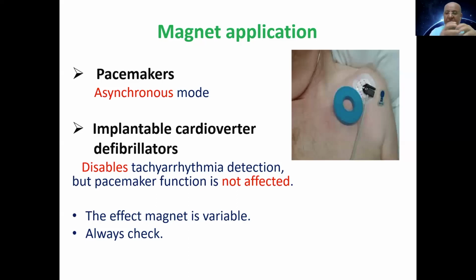So when a magnet is applied to the pacemaker, it will shift it to asynchronous mode, as we mentioned before. The effect on the ICD is different. A very important point: on the ICD, the magnet will disable the tachyarrhythmia detection. Okay, it's good, but it has no effect on the pacemaker function of the ICD.